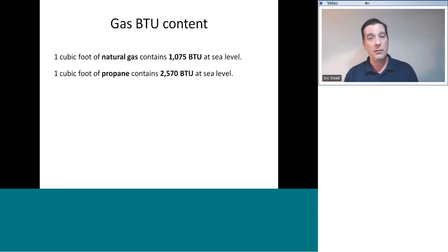1 cubic foot of propane, by comparison, contains 2,570 BTU at sea level. And we'll round this off to about 2,500. So you can write that off to the side, round that off to about 2,500 BTU per cubic foot. Once again, if you are in a propane marketplace, different propane suppliers may be supplying different types of gas at different locations. So it's a good idea to call up and ask the propane provider what is the caloric value of the gas that they're providing. And sometimes it may change from time to time.